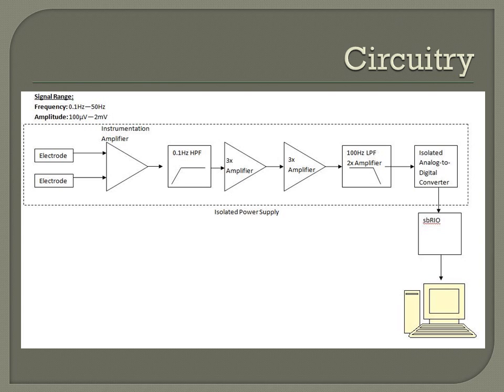Here's a basic flowchart of the circuitry involved in an EOG. The electrodes go into an amplifier, which goes into a high-pass filter. This is then amplified a few times, after which the signal is fed through a low-pass filter, and then it's isolated to an analog-to-digital converter, which is then read by a computer.